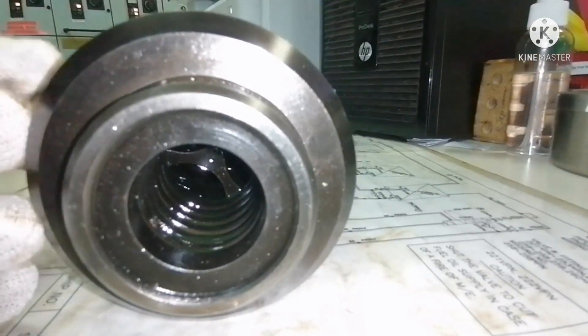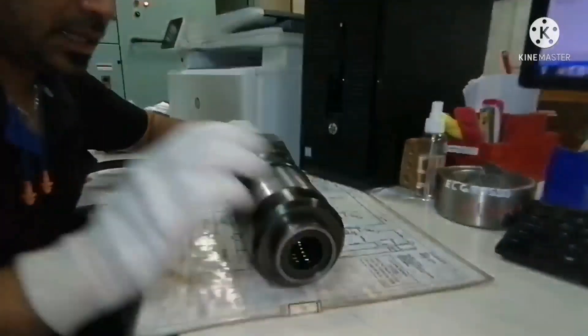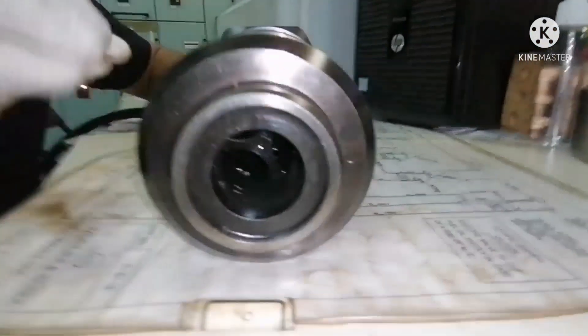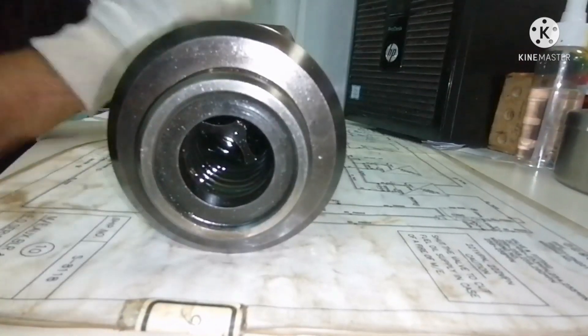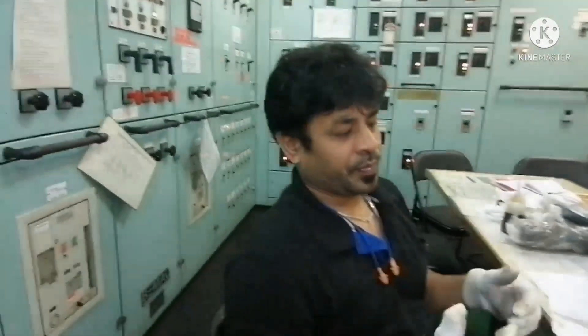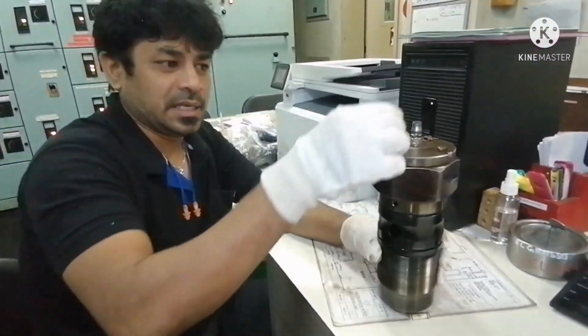So this is what we have to check — this is how we check whether your puncture valve is working fine or not. We just need to connect the air and see that the valve guide is pushing towards the spring. And when you remove the air, it has to go back. That's all. This is the test we need to do for checking your puncture valve.